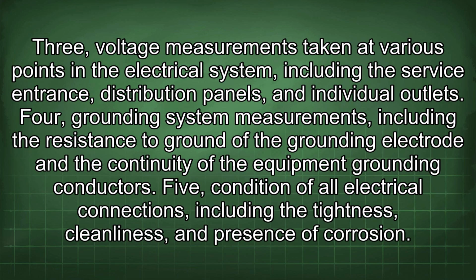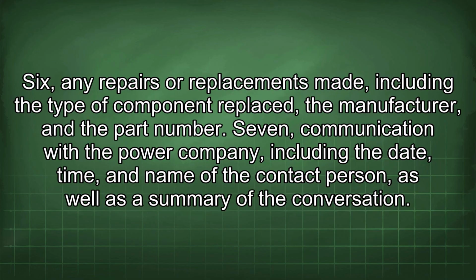3. Voltage measurements taken at various points in the electrical system, including the service entrance, distribution panels, and individual outlets. 4. Grounding system measurements, including the resistance to ground of the grounding electrode and the continuity of the equipment grounding conductors. 5. Condition of all electrical connections, including the tightness, cleanliness, and presence of corrosion. 6. Any repairs or replacements made, including the type of component replaced, the manufacturer, and the part number.